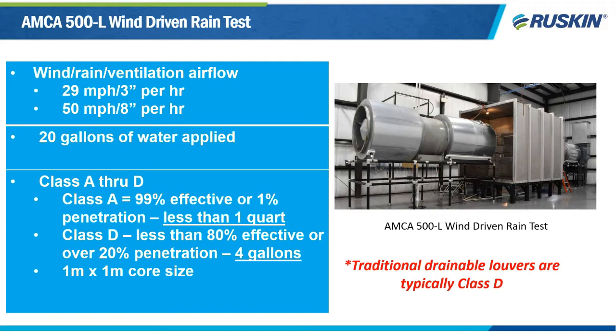The core is the face area of the louver minus its perimeter frames. The standard size that we test in this is 1 meter by 1 meter core, which can equate to roughly 42 inches by 42 inches OD, depending on the frame width. And there are two levels of weather that we test in, a standard level with 29 mile per hour wind and 3 inch per hour rainfall, and a higher level of 50 miles per hour wind and 8 inches per hour rainfall. Louvers are tested at various ventilation airflow levels, beginning with no airflow and going up through 5 meters per second core velocity. And they receive a letter rating, class A through D.